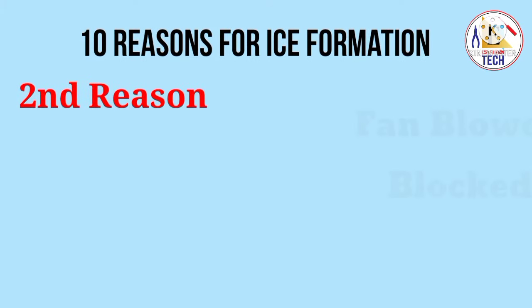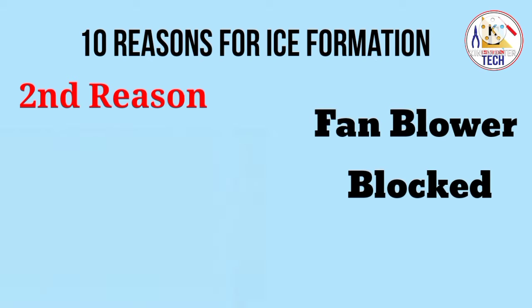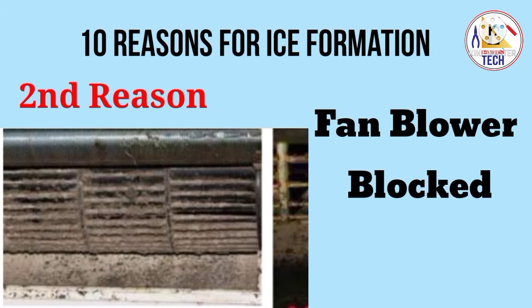The second reason for ice formation is the fan blower. If our fan blower is blocked or totally dirty and the air flow is low during operation, the unit will make ice and you will get water leakage, low cooling, and low air flow. To avoid this, clean the blower frequently to get proper cooling and prevent ice formation in your indoor unit.